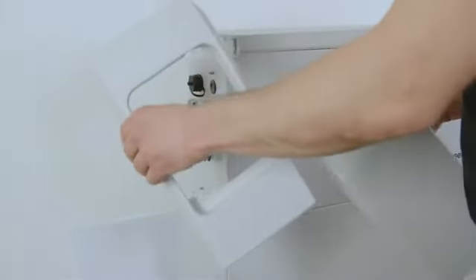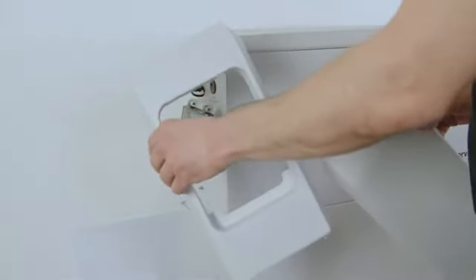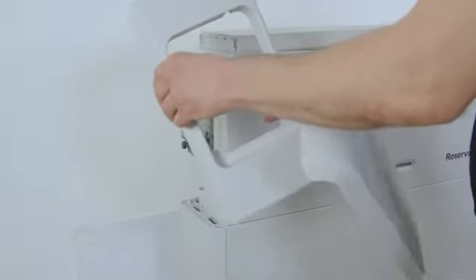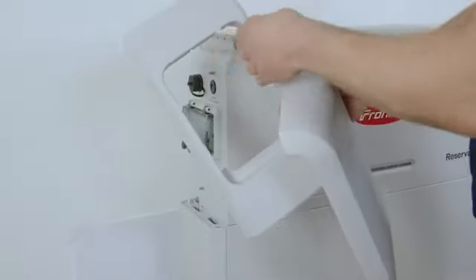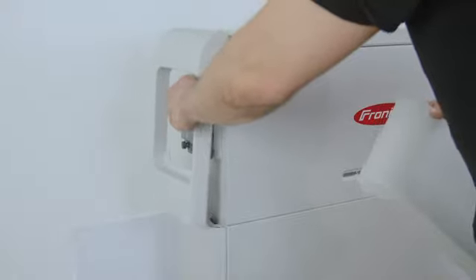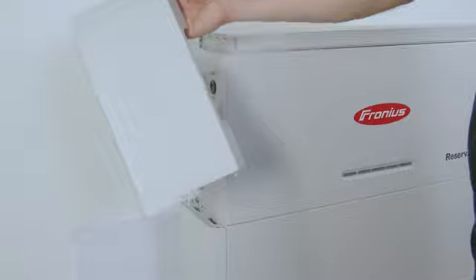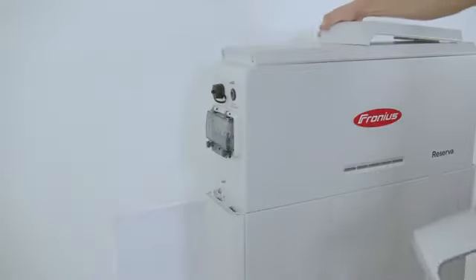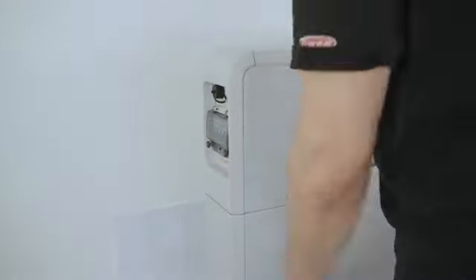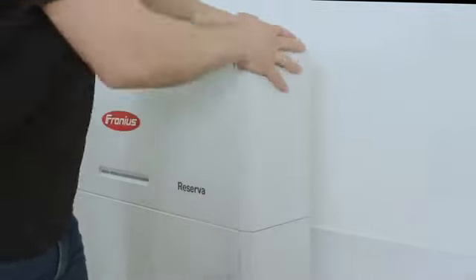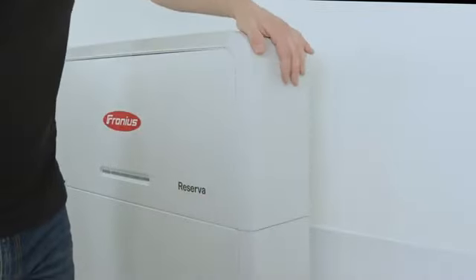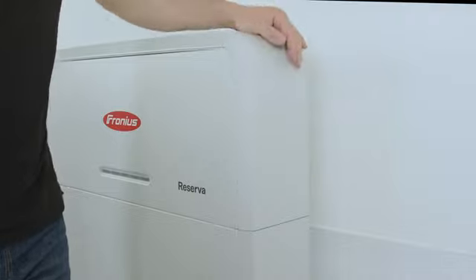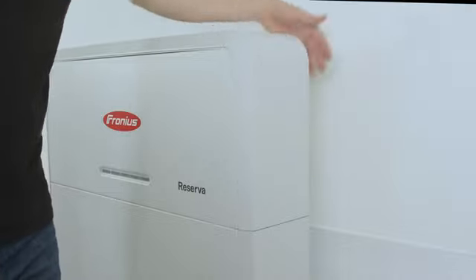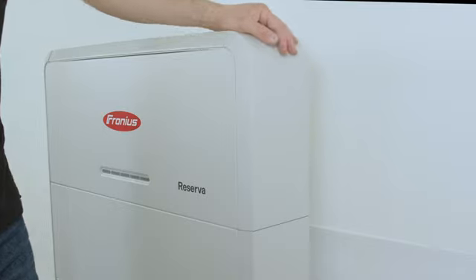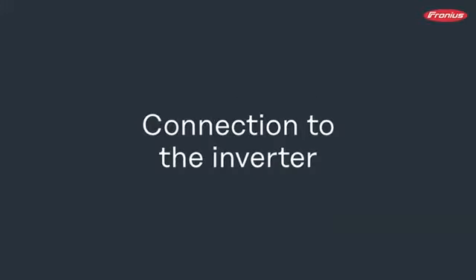Last but not least, we install the left and right hand side cover of the battery management system, and therefore we have one bigger module with a hole in the middle, and this is installed to the left side of the battery module, whereas the other module is installed to the right side to cover the cable. After installing the last cover for the connection area, now the cabling is on the back side of the Reserva, and now it is protected against mechanical harm.